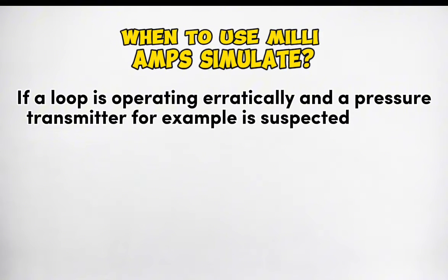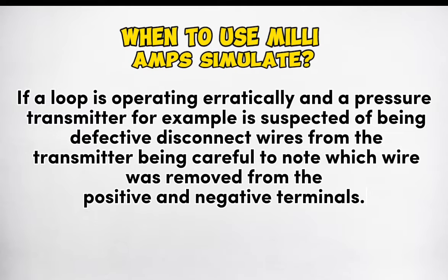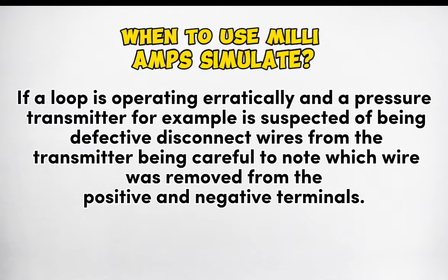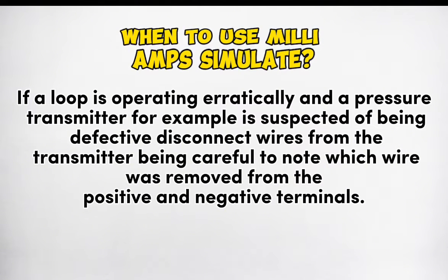When to use milliamp simulate: if a loop is operating erratically and a pressure transmitter, for example, is suspected of being defective, disconnect the wires from the transmitter, being careful to note which wire was removed from the positive and negative terminals.